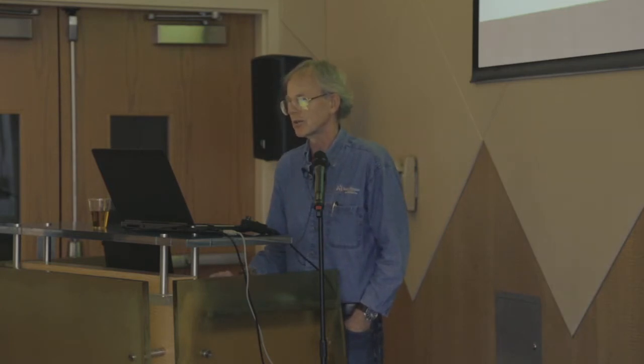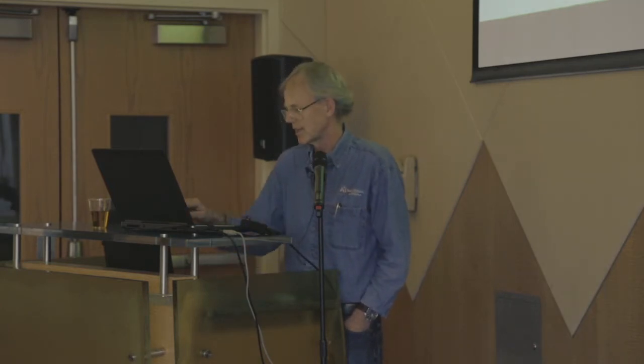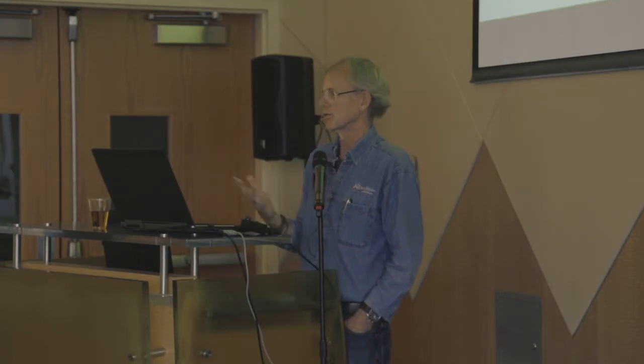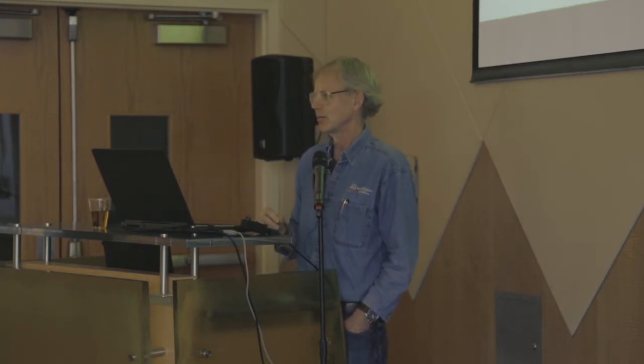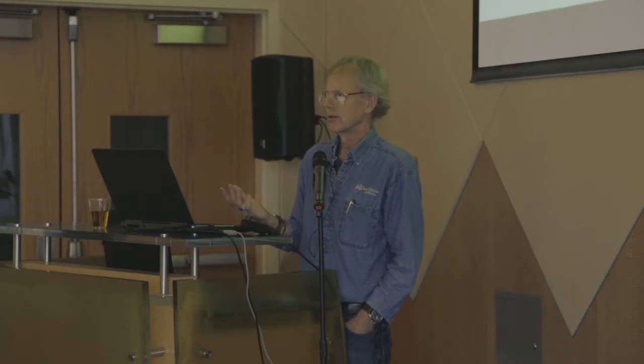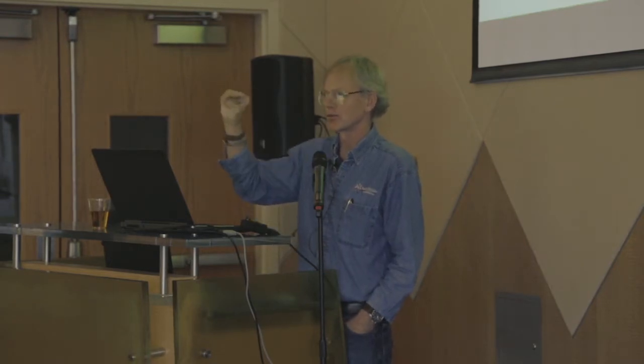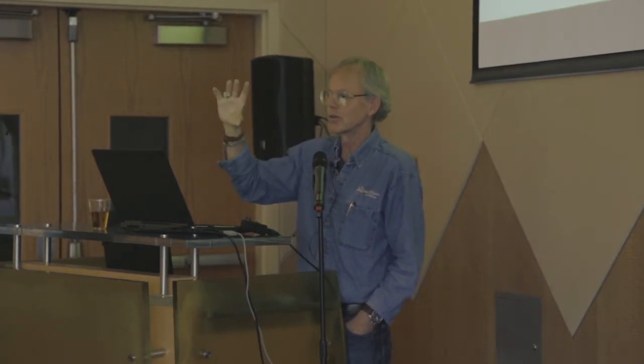If I got crazy with the proportional band, what do you think would happen if I narrowed the proportional band down to like 10? What would you expect? Slower actions. Go unstable, you make it smaller. In other words, the range over which the control signal is going to react is smaller.